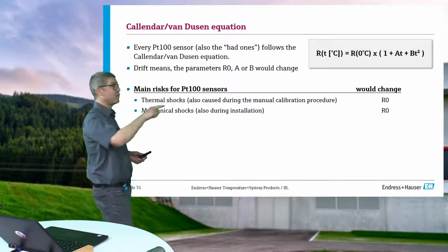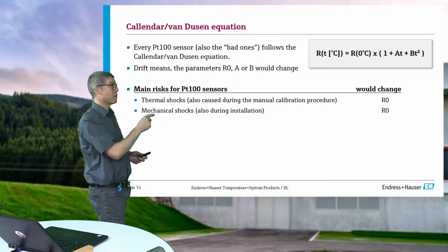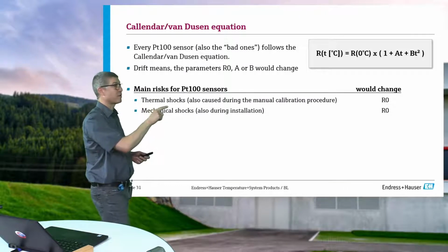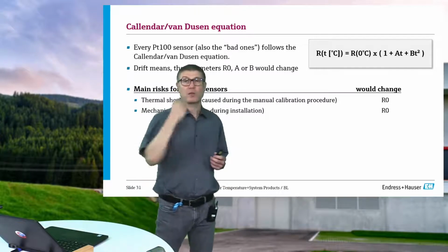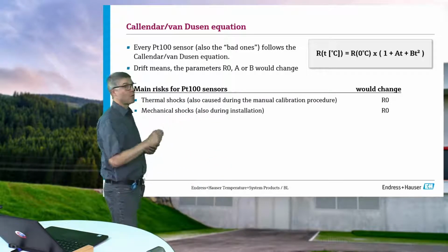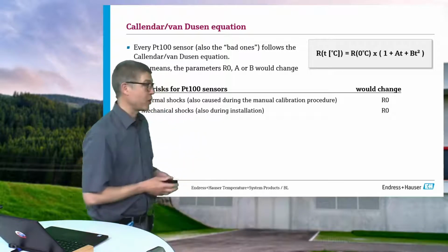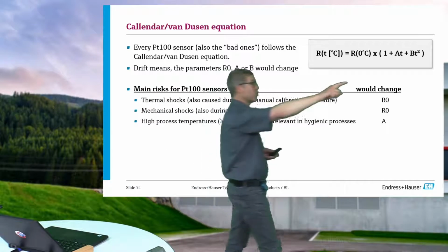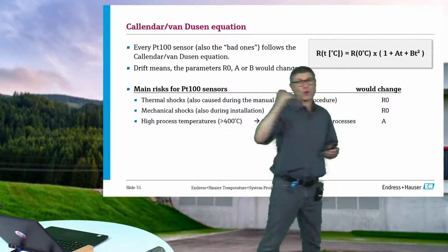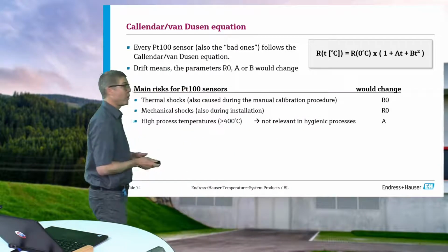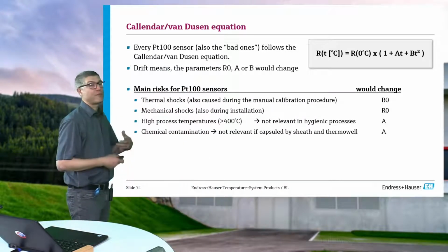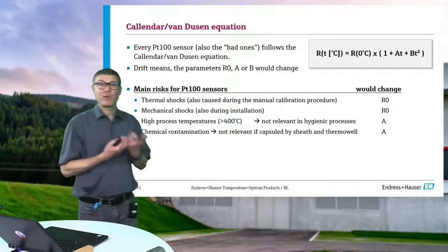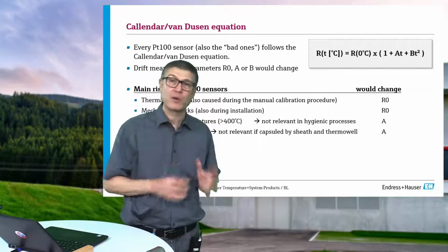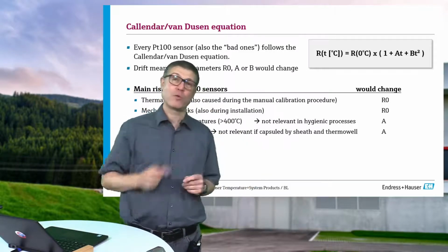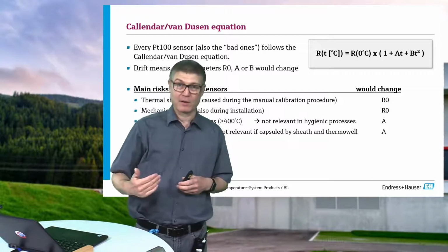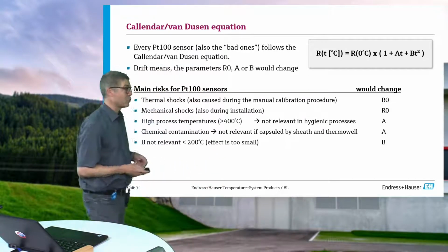And the main influence in your applications, food and beverage and life science, are thermal shocks, if you place your sensor into a hot calibration bath, or mechanical shocks if it falls down after your calibration. The other influences which are changing the curve are only relevant at higher temperatures, or if you have a chemical contamination of the platinum sensor itself. And how can you go to the platinum inside? There are 2 layers of stainless steel. So whatever you do, you won't be able to touch the sensor.